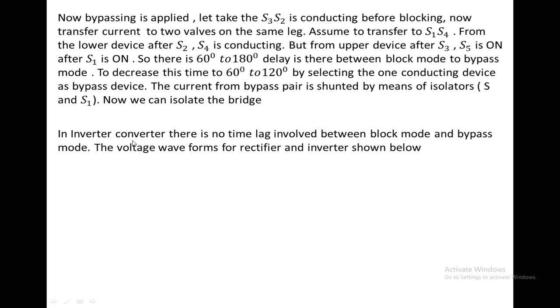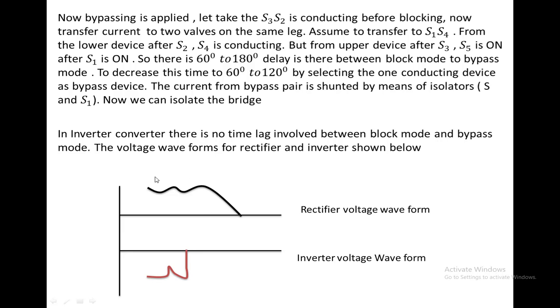In the case of an inverter converter, there is no time lag between blocking mode and bypass mode. The voltage waveforms of rectifier and inverter modes are shown below. For the rectifier, after initiating blocking, the current comes to zero with some delay. But in the case of the inverter, after initiating blocking mode, the voltage directly comes to zero. This is the difference in de-energization between the rectifier converter and the inverter converter.